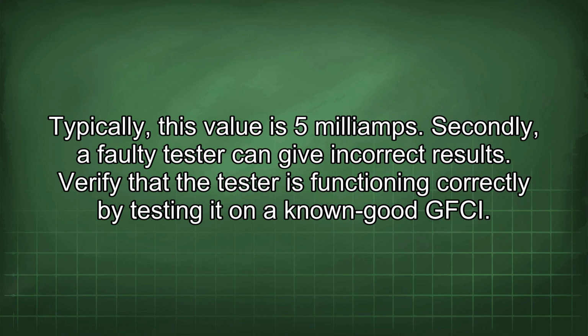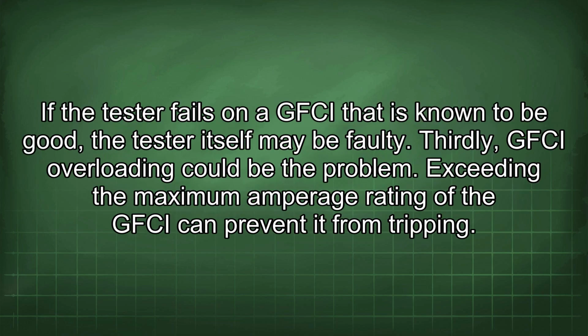Secondly, a faulty tester can give incorrect results. Verify that the tester is functioning correctly by testing it on a known good GFCI. If the tester fails on a GFCI that is known to be good, the tester itself may be faulty.